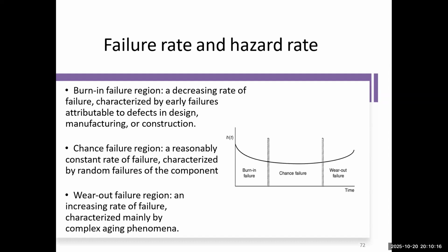Okay, so let's consider a real-world example, such as an automatic fire pump in a high-rise building. In the burn-in phase, shortly after installation, there is a higher chance of failure. Perhaps a seal wasn't fitted correctly, or a wiring connection is loose. These issues tend to show up quickly. And then we have our chance failure phase. For years afterward, the pump operates reliably.